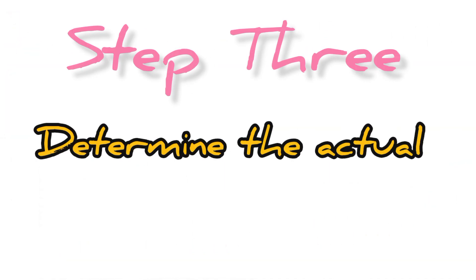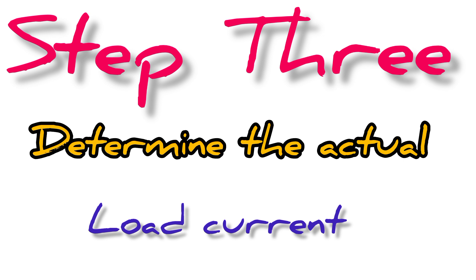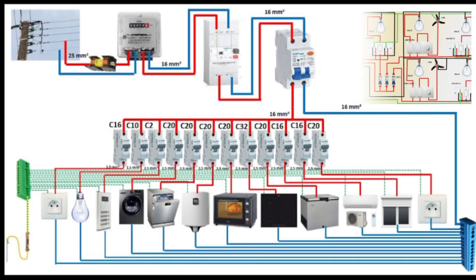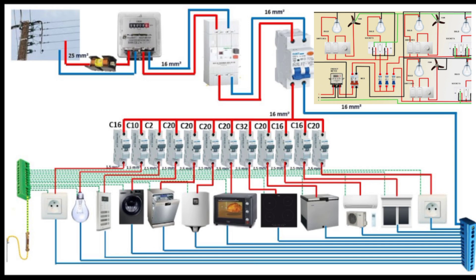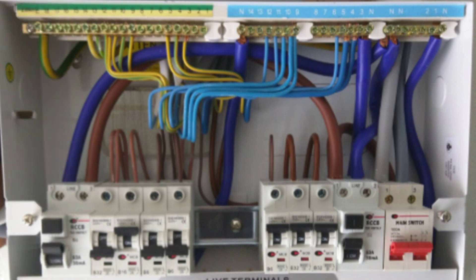The next step is to determine the current rating of the load demand. It is actually the current we are after in this calculation. We assume that all appliances will not operate at 100% efficiency, so we consider power factor. The current formula is: Current = Power divided by (Voltage times Power Factor). Typically in residential loads, power factor ranges between 0.85 to 0.95. We look for current because we want to know what size of cable can safely carry that amount of current.